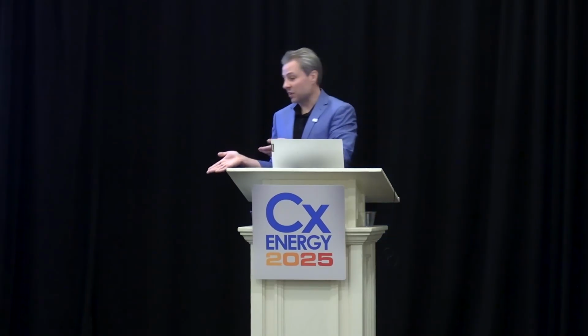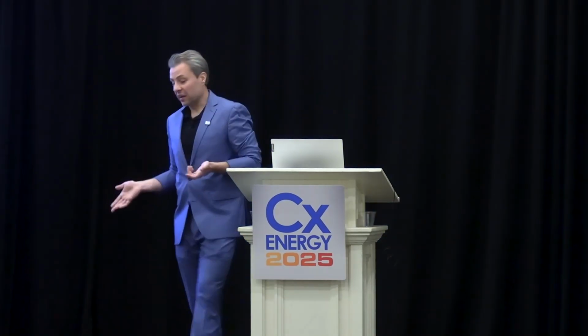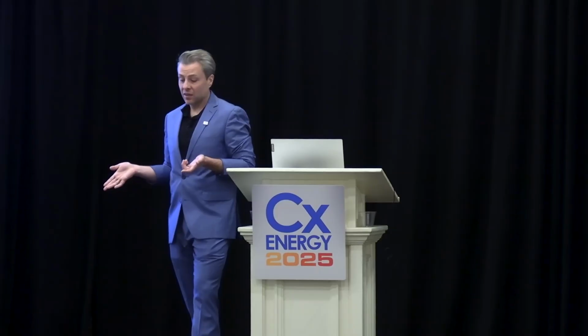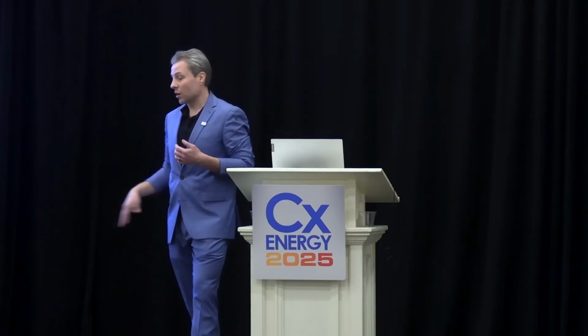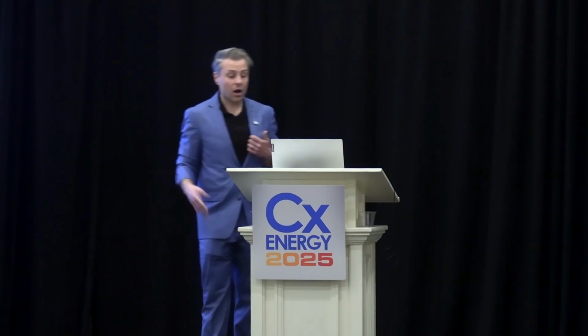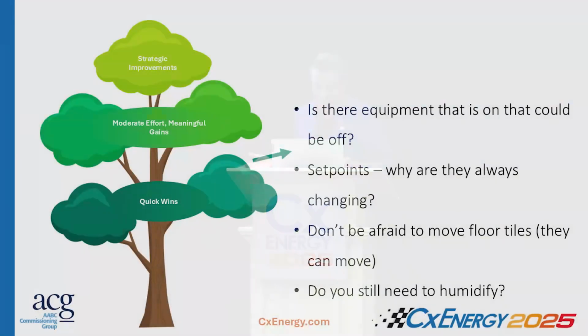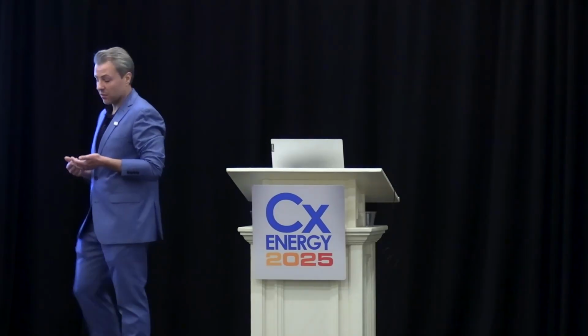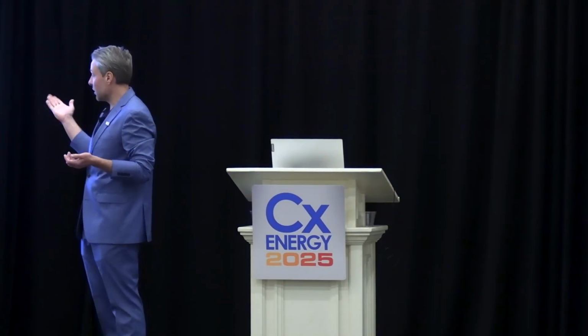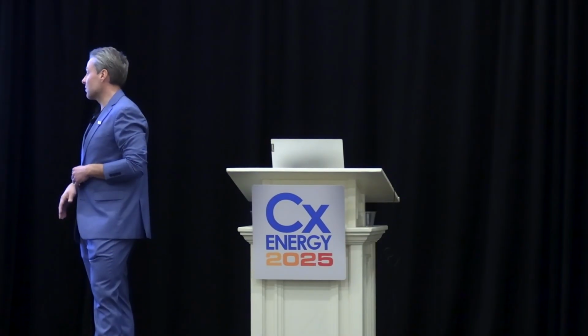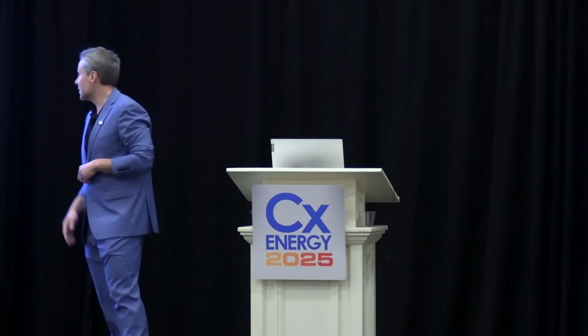Now, that wasn't an energy savings component, but as far as resiliency and uptime, if they'd added another computer, there's a good chance it would have gone into thermal overload from being too hot to run. So for set points, we know what the design values are—let's make sure we're maintaining those and that the facility is running at the optimal, designed temperature. It might not be the best for energy savings, but for uptime and resilience, the number one factor is keeping it running.